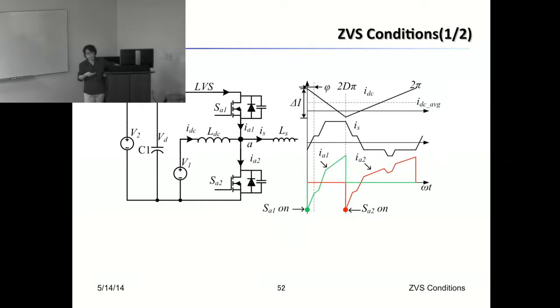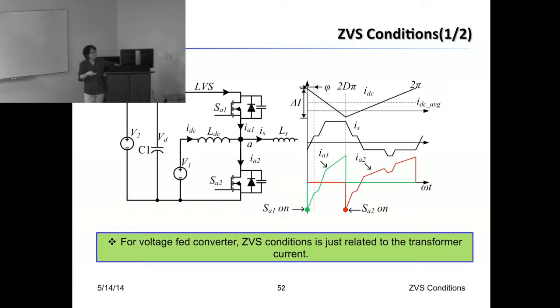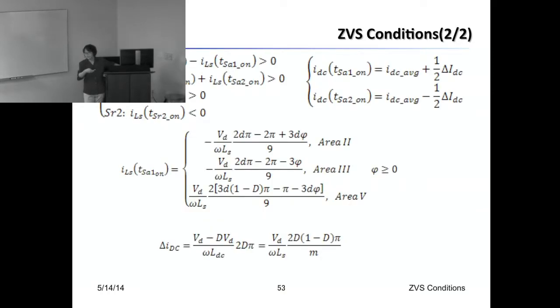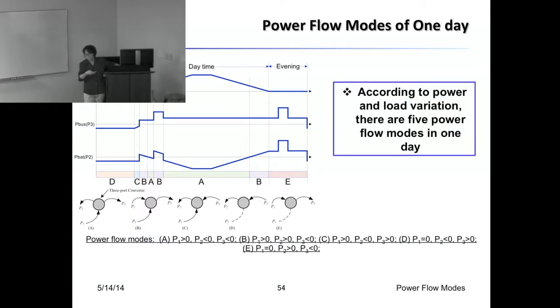Also the zero voltage switching condition becomes complicated. For voltage fed, it's only related to the transformer current, but now it's related to the DC inductor current as well as the transformer current. Also, if you connect the battery to the DC link, the battery's charge-discharge voltage variation also affects ZVS.